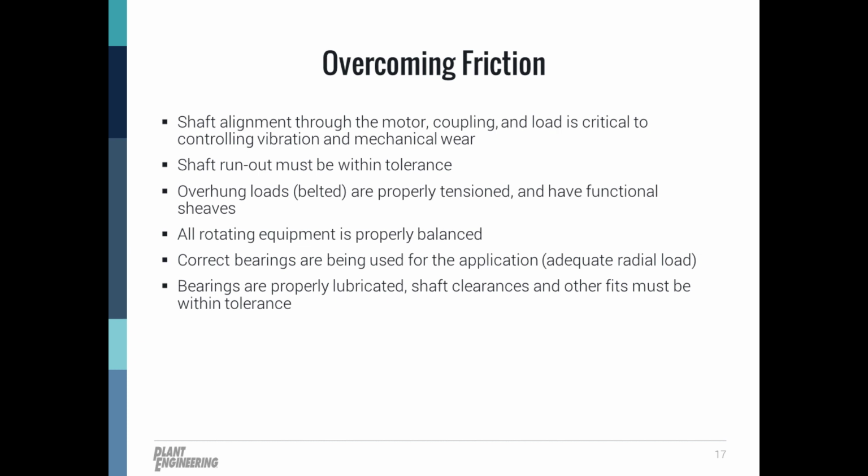But just to reiterate, bearings are the number one cause of motor failure. So it is very important to follow preventive maintenance routines with your bearings, such as periodic lubrication and vibration analysis. Even when greasing the bearings, verify the proper lubricant is being used and the proper amount of lubricant is being added. The most recommended grease type that we see these days in the field is Polyrex EM.